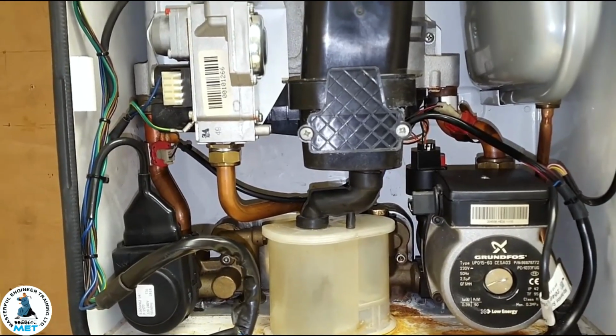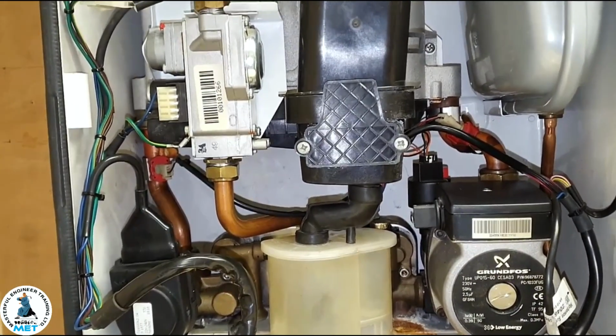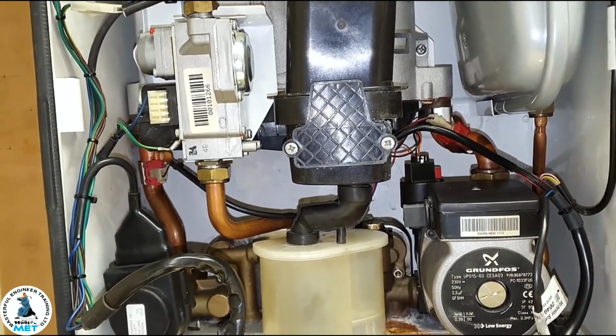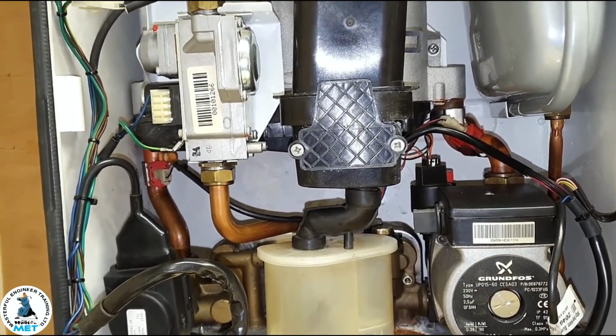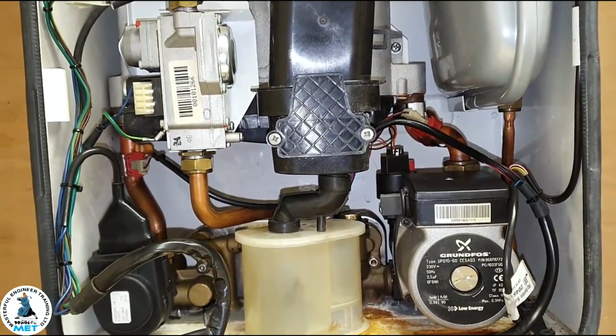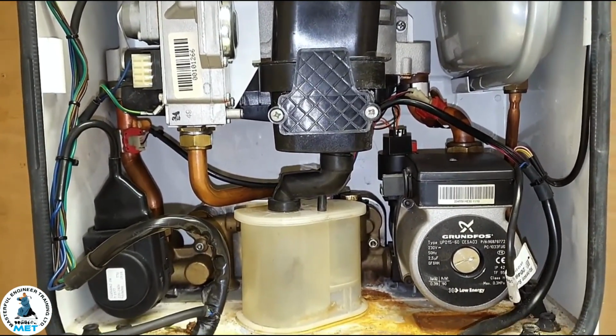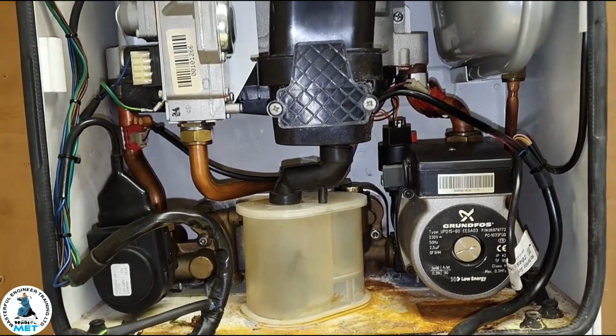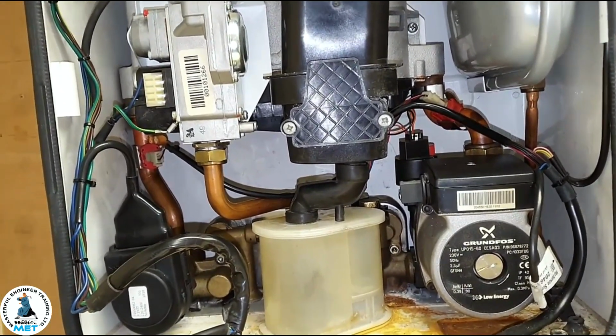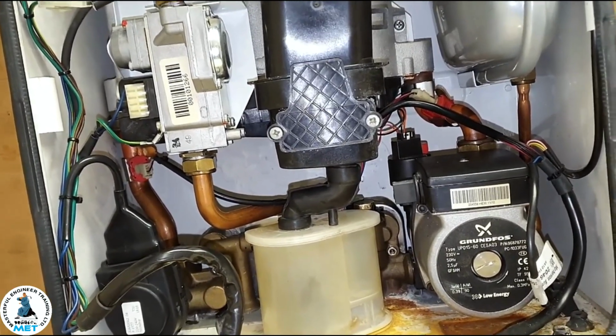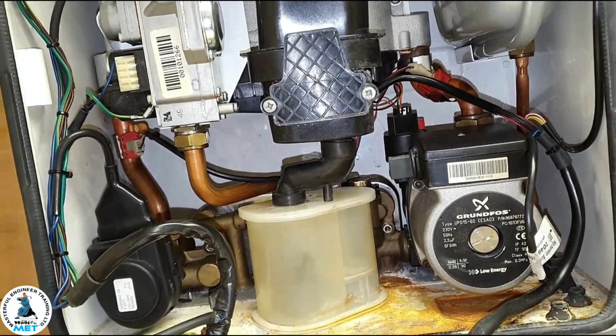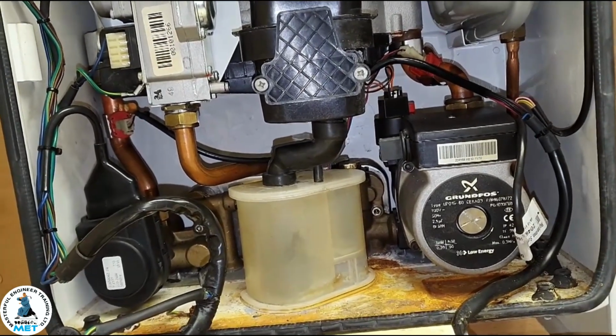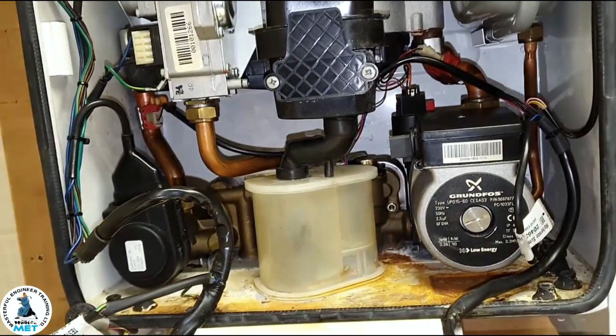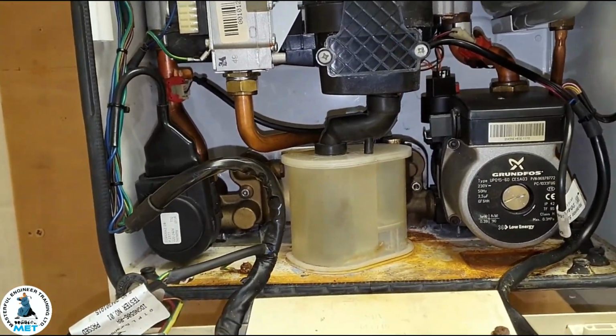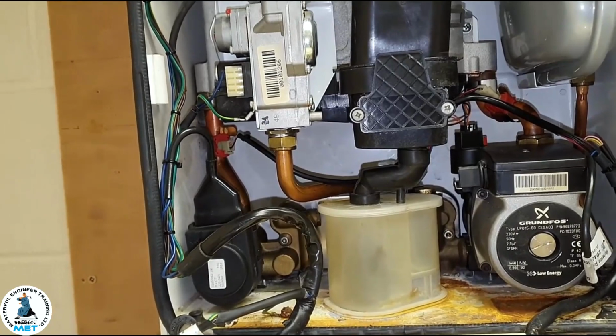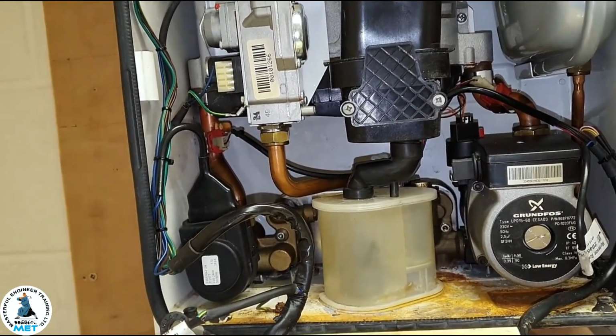Right, okay, when the pressure's going up, you're going to check your gauge. The customer might be alerted that the pressure's gone up, or you might be alerted to that. Now the pressure can go up in basically two ways. You've got to weigh things up, so you've got when the boiler's on and working, and when the boiler's off and not working. You've got to determine what's going on, and again, the art of listening to the customer is going to give you the clues.